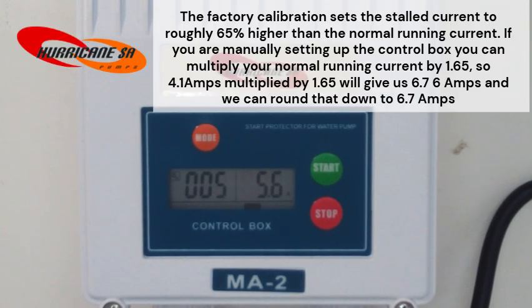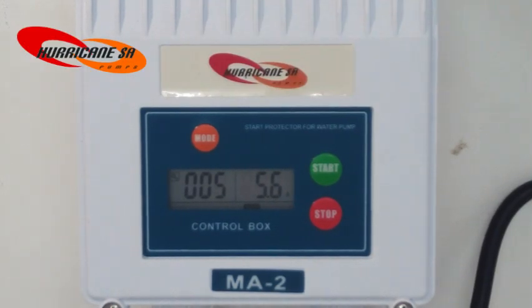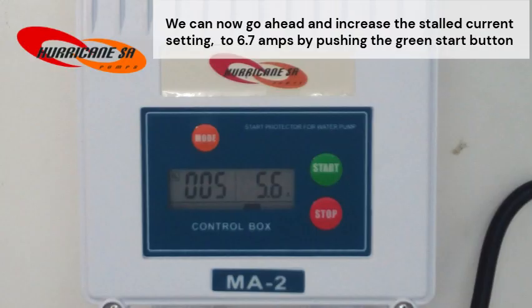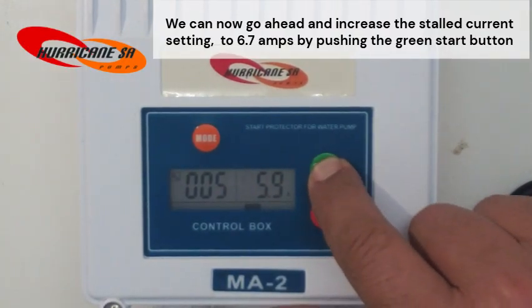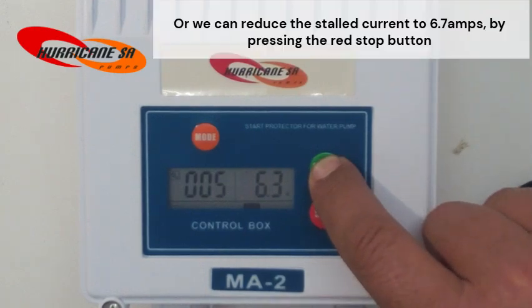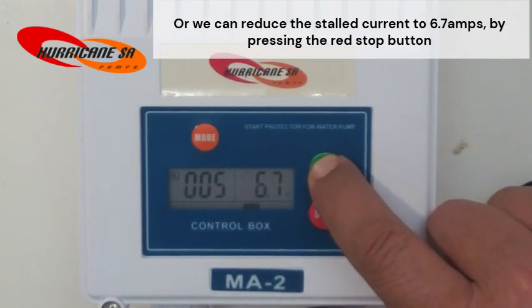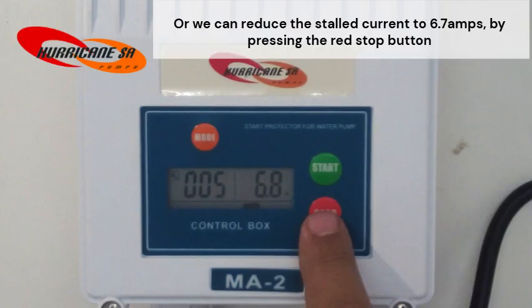If you are manually setting up the control box, you can multiply your normal running current by 1.65. So 4.1 amps multiplied by 1.65 will give us 6.76 amps, and we can round that down to 6.7 amps. We can now go ahead and increase the stalled current setting to 6.7 amps by pushing the green start button. Or we can reduce the stalled current by pressing the red stop button.